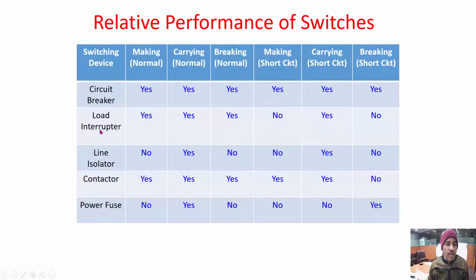But what is a load interrupter? A load interrupter can make, carry and break under normal conditions. But it cannot connect under short circuit conditions. It can carry short circuit currents, but it cannot break under short circuit conditions. This is what is known as a load interrupter. So it can work under normal conditions properly, and it can carry abnormal current, but cannot make or break abnormal currents. That's what the load interrupter can do.